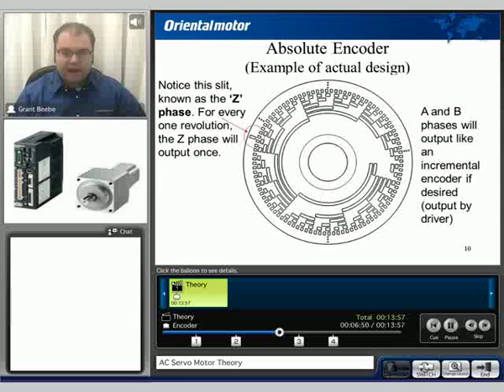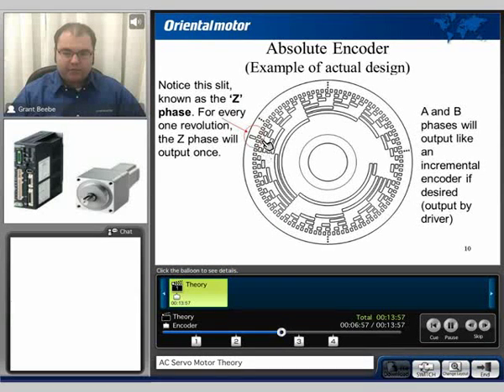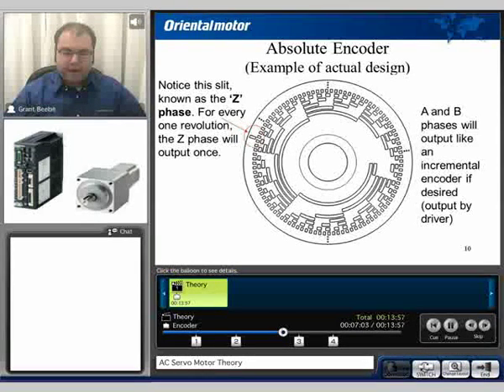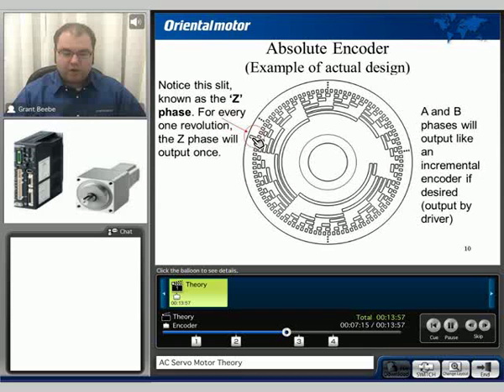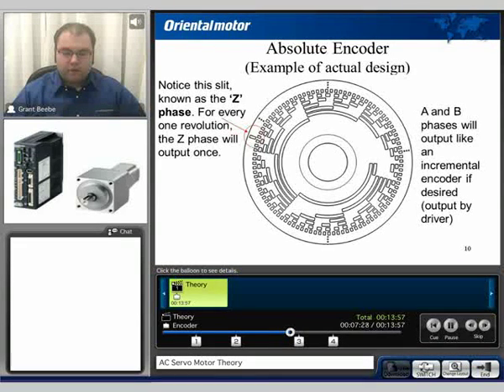Here is an example of an actual design of an absolute encoder. We can see that on the outermost portion we have the single digit, then the next digit, and the next digit, and so on — outputting a binary scheme. Also notice that once per revolution there is what is known as the Z phase, which outputs one pulse per revolution. We can use that to keep track of information for homing and for other more precise movements. The A and B phases output like an incremental encoder, in the exact same fashion, typically output by the driver.